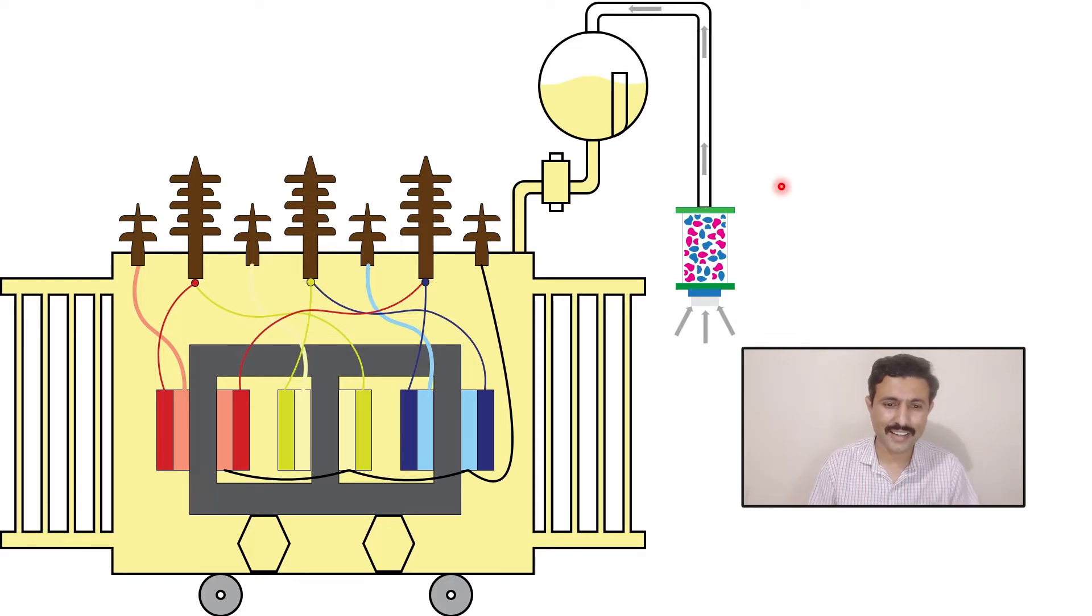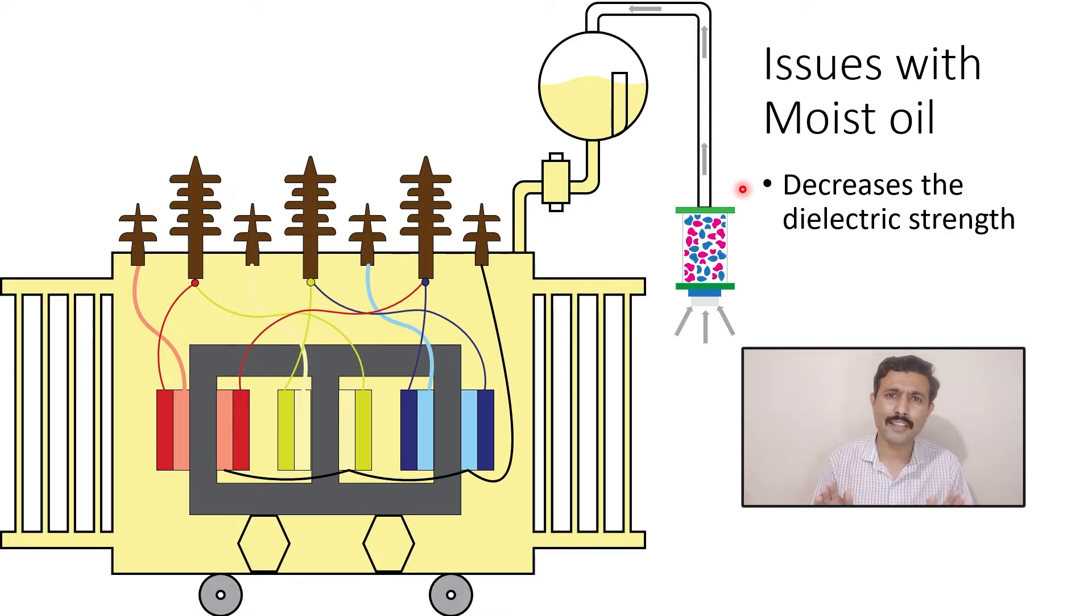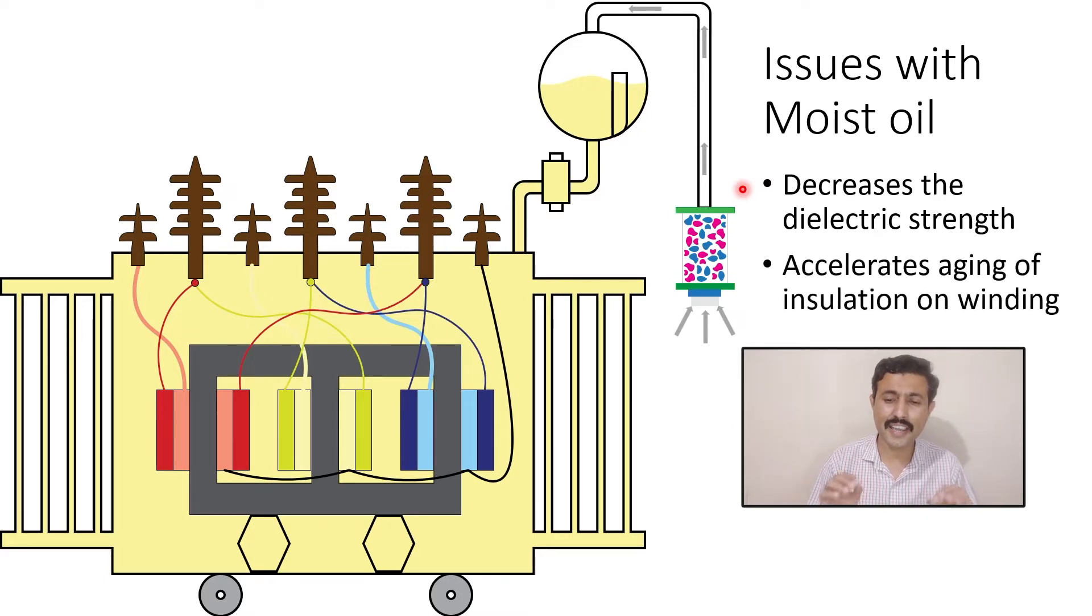When that moistured air mixes with the oil, it will create issues. When moisture in the air mixes with the oil, it decreases the dielectric strength of the oil. If the dielectric strength of the oil reduces, it creates lots of issues for transformer. The other problem is it accelerates the aging of insulation on the winding.